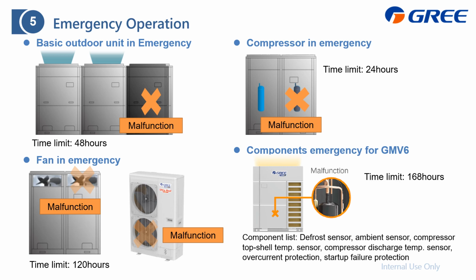So we just allow you to apply this mode or the emergency to shield it off, and the system can still operate. And on the other hand, not only for the components, but also for the overcurrent protection and startup failure protection. That means if the system detected, for example, during 1 hour, there are 3 startup failure protections, then the system will lock down.